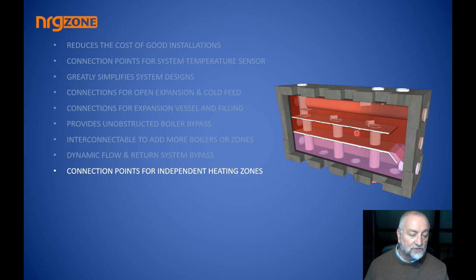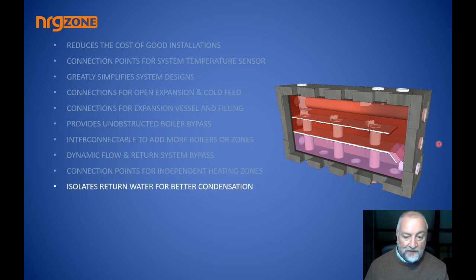And again, just to repeat, you can only connect the flow onto where the boilers are delivering the heat into, and you connect your return back to the chamber that the boilers are returning back from. And then the water isolation, we've mentioned that with the buffer tank. We've spoken about stratification: the hottest water is contained as it passes through and drawn away for zones and whatever, and the return water is also captured in a stratified position where it can be drawn back by whatever appliance you've decided you wanted to let it be drawn back to.